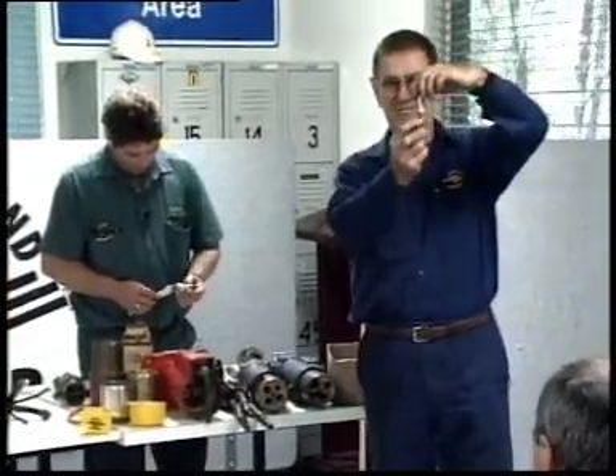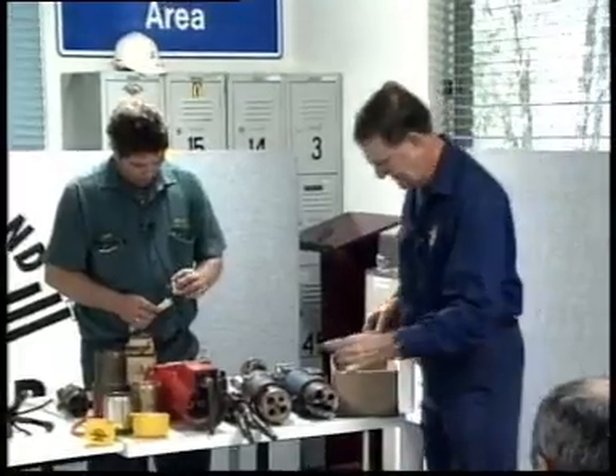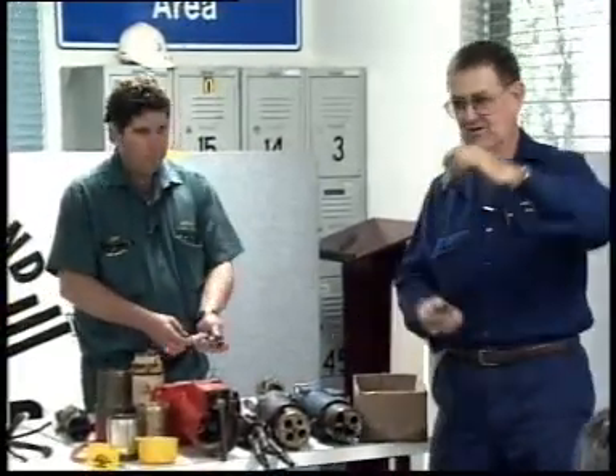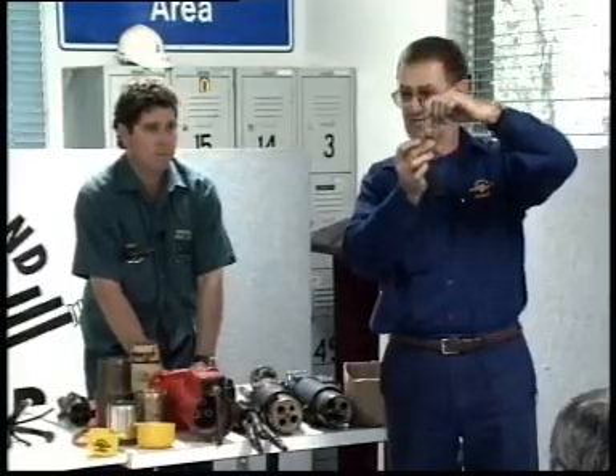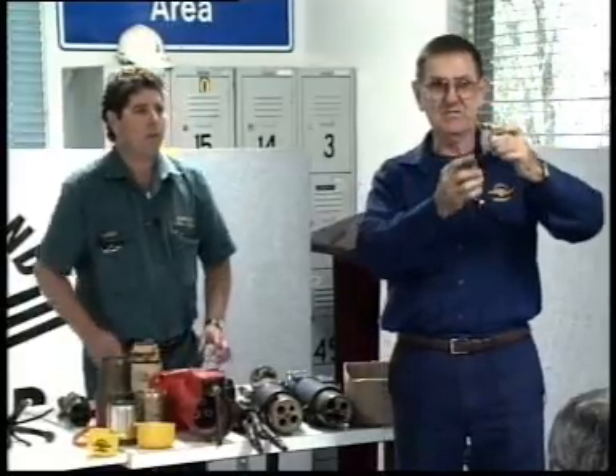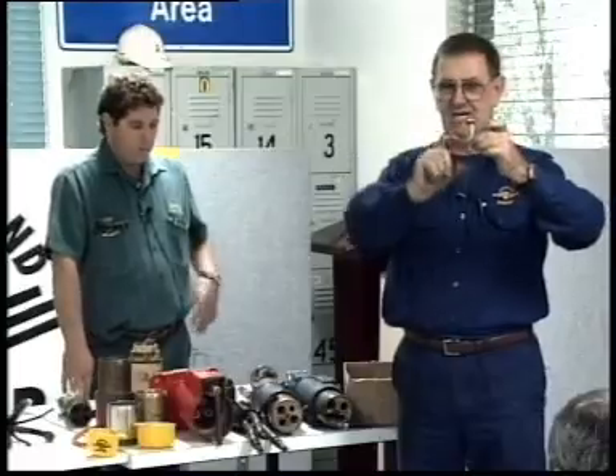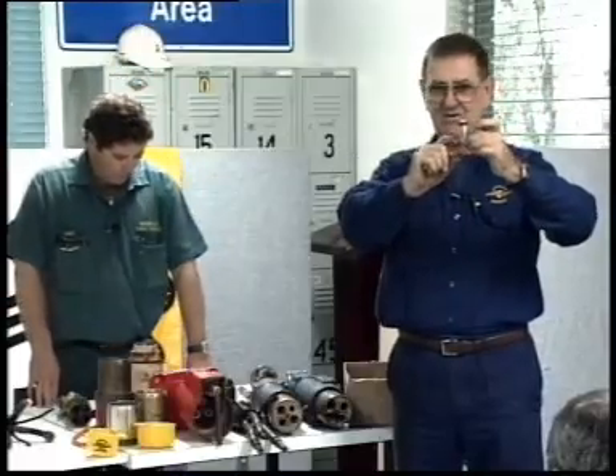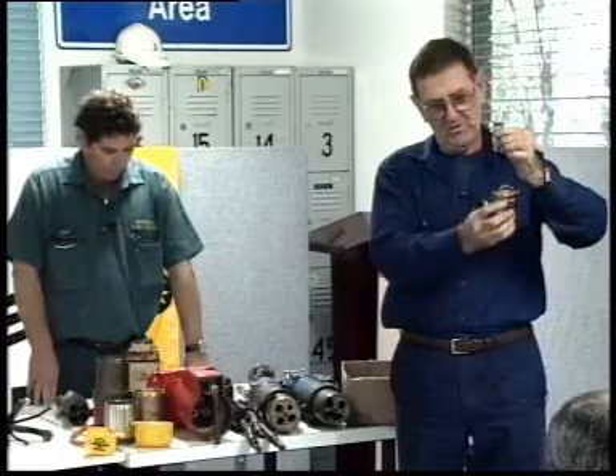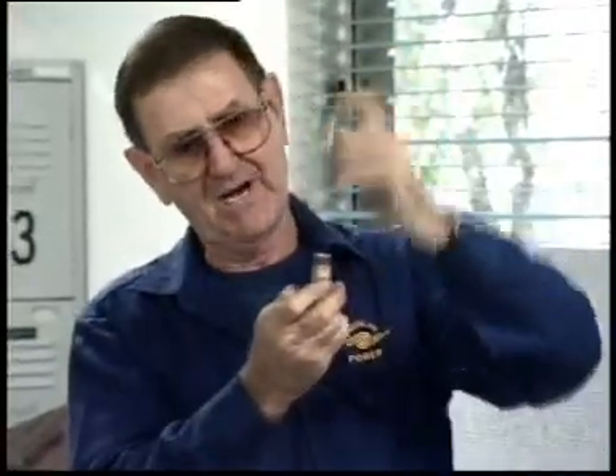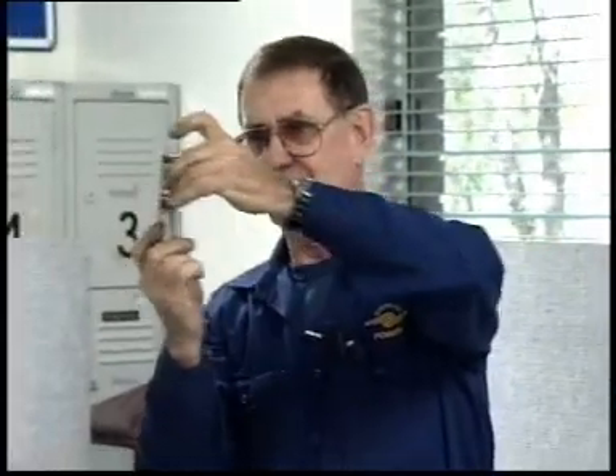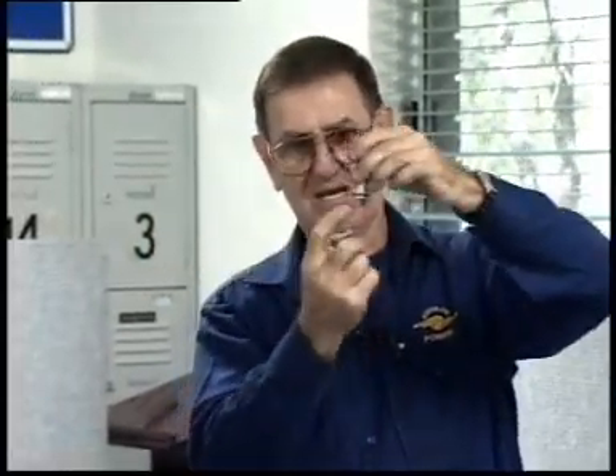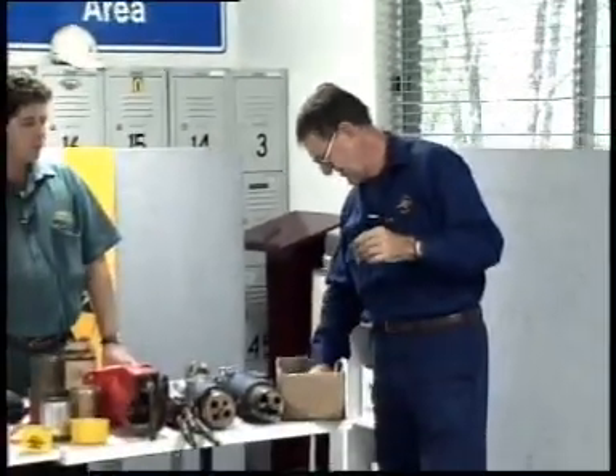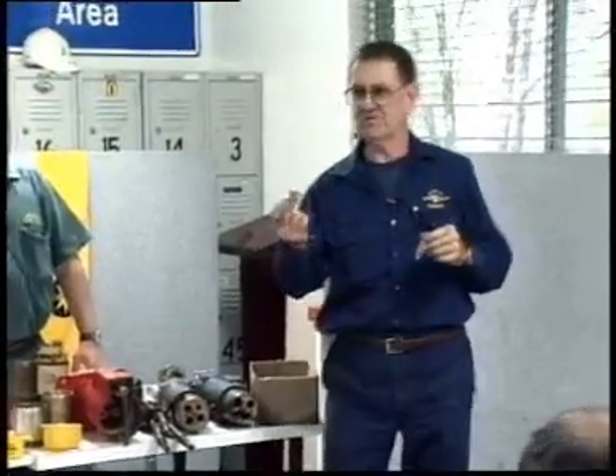This little tapered section here, where it goes in the front end of the plug, it comes down onto the female contact that's in the back, and it goes up on the tapered section and locks. Some people have been changing the screws in there at the mine sites, and they haven't been using the correct length screw. It's been too long. So it's been pulling the female one up, or screwing down in the female one at the back and bottoming out before it actually puts them together and makes a good connection on the taper. So you start getting burning around this tapered section. You also get burning on the screw that's holding it if it's the wrong screw, and all the current will go up the screw and burn the screw away.